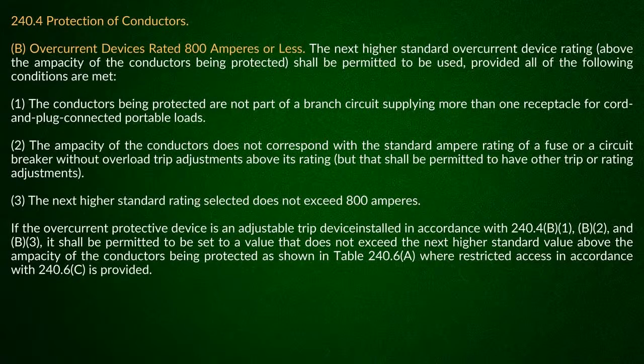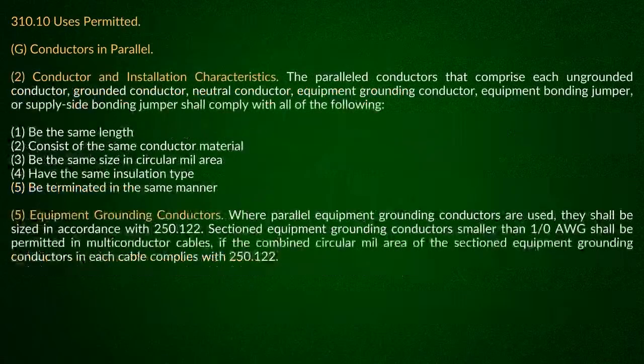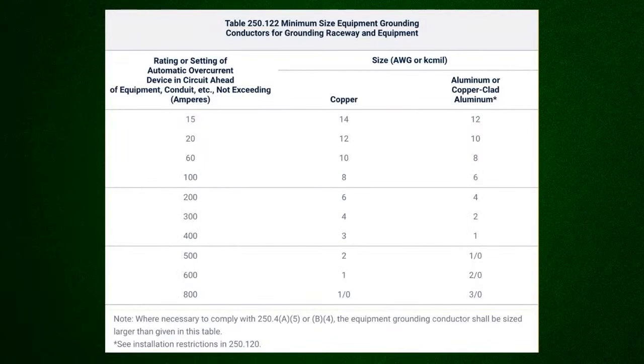And I'll say this. If he turns it up, it's no longer based on the 600 amp overcurrent device. It's based on the conductor. So the size of the equipment ground would be based on a 700 amp overcurrent protection device and not a 600 anymore. If I go to the table real quick and look at a 600 amp, and let's just say he's using aluminum, it's a 2/0. But as soon as I go up above that, now you would have needed a 3/0 equipment grounding conductor.